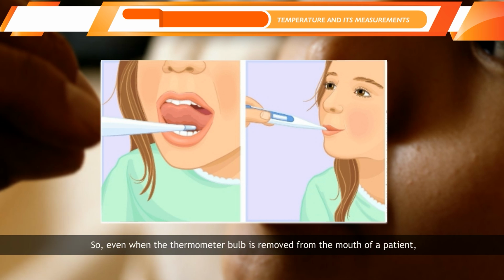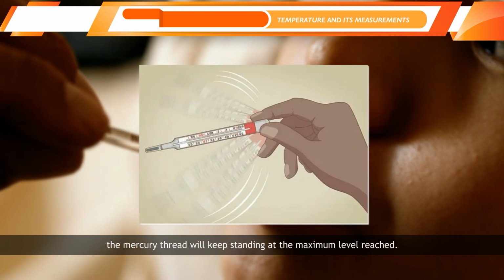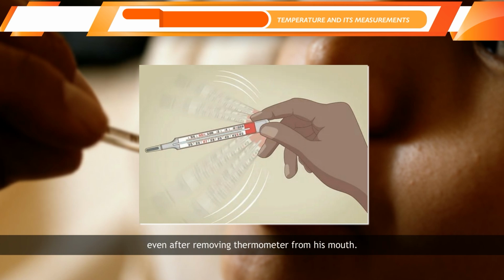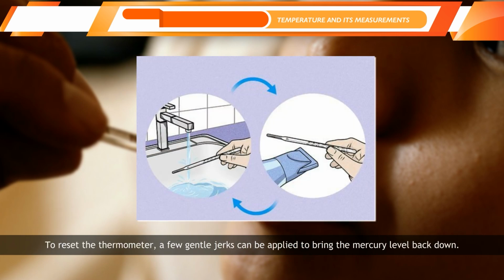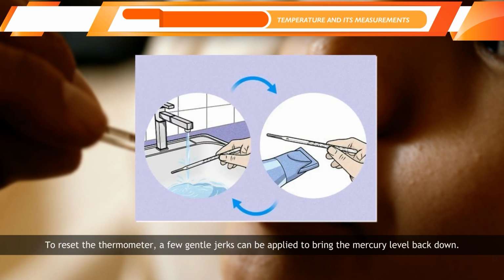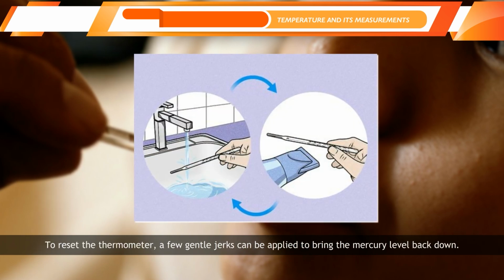So even when the thermometer bulb is removed from the mouth of a patient, the mercury thread will keep standing at the maximum level reached. Due to this, we can read the correct body temperature of the patient even after removing the thermometer from his mouth. To reset the thermometer, a few gentle jerks can be applied to bring the mercury level back down.